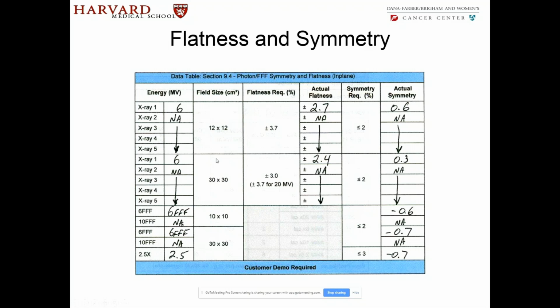Again, this is for 6. For 6 FFF, there is no flatness requirement, only a symmetry requirement. Symmetry has to be less than 2%. For 2.5, because it is an imaging field, it's less than 3%. You look at the field sizes, check it out: 12 by 12, 30 by 30, 10 by 10, and 30 by 30. This region is vacant because for 6 FFF and 2.5, there is no filter in there which will flatten the beam. As you can see here, the actual flatness was 2.7, so it is within their tolerance of 3%. We sign off on it, we accept it.